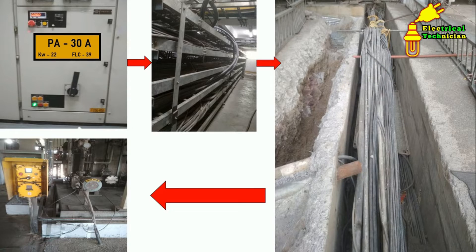What happened in our company — somehow this motor got tripped due to earth fault. A task was given to us to identify the reason this motor tripped. When we took the IR value, we came to know the core of the red phase is short with the earth — somehow connected to earth. This is why the motor tripped due to earth fault.